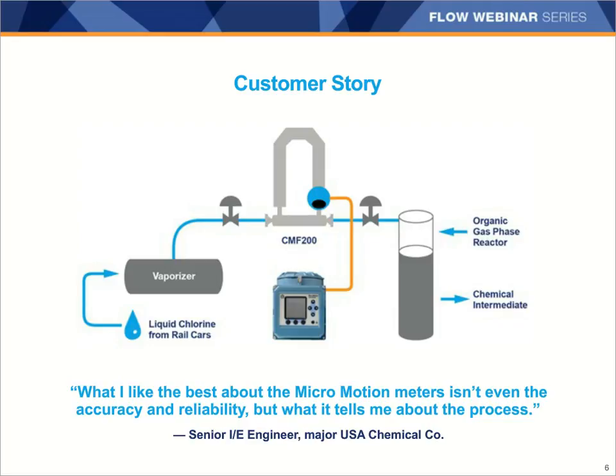After he weighed multiple options, they ended up choosing a 2-inch Micro Motion Elite Coriolis mass flow meter that not only was able to accurately measure the chlorine and help keep the reaction in control in the first place, but it could also tell them if the flow ever changed direction in the meter or if there was any kind of liquid in the line. So they used the density as a diagnostic in this situation. As shown in this quote, the customer really valued the process information that they got from the meter even more than the accuracy and the reliability that they got from the Micro Motion meter.